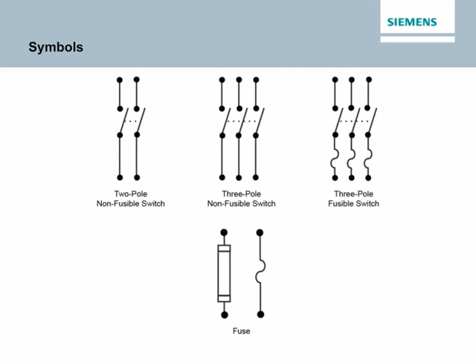A safety switch with no associated fuses is referred to as a non-fusible safety switch. A non-fusible safety switch has no circuit protection capability. It simply provides a convenient means to open and close a circuit. Opening the circuit disconnects the load from its source of electrical power, and closing the circuit connects the load. Circuit protection must be provided by external overcurrent devices such as a circuit breaker or fuses. In the top illustration, power is supplied to a motor through a non-fusible safety switch and a separate fuse.